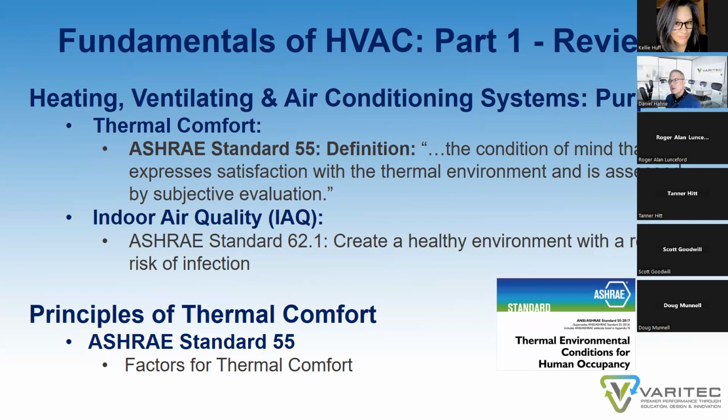In the last session, we looked at thermal comfort, and we brought forward ASHRAE Standard 55's somewhat scientific definition of thermal comfort as being the condition of mind that expresses satisfaction with the thermal environment and is assessed by subjective evaluation. I think we mentioned at that time that a building is properly designed if 80% of the occupants in the building are satisfied. You can never provide a design that provides 100% satisfaction for all the occupants, for reasons we covered in last month's session.